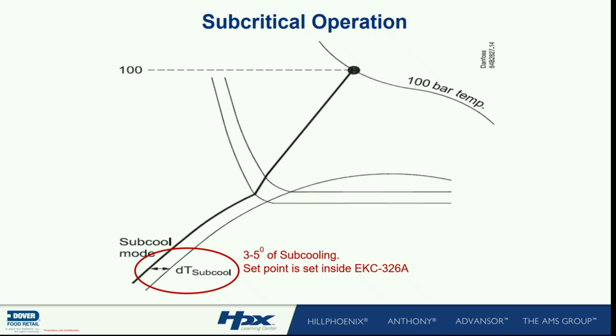That's 87.7. So everything out here is subcool, everything over here is superheat - sorry, everything over here is subcritical if it's above that line. Everything inside here is saturated, meaning it's a liquid vapor mixture. So what we're doing is saying, okay, if I want 3 to 5 degrees, depending on who set it up, I can draw this line.